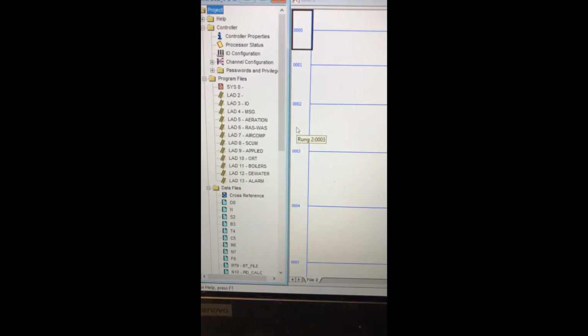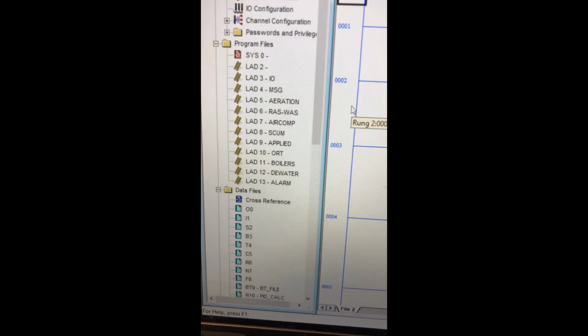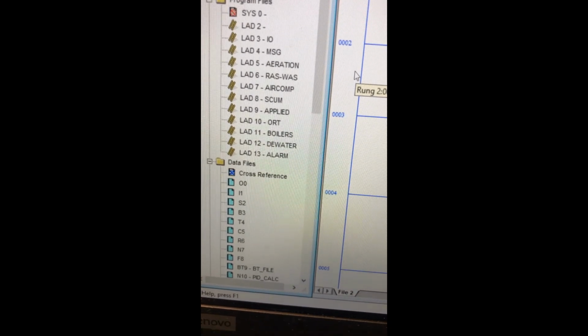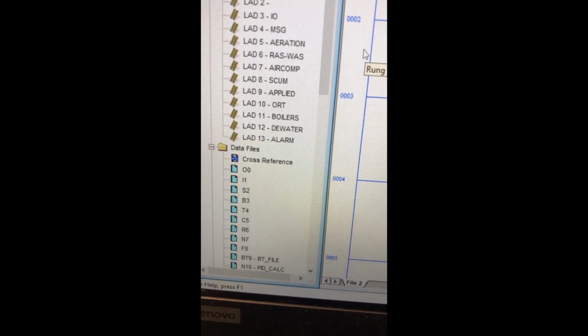So this is where I do all the PLC programming. This is what the software looks like for Allen-Bradley. And this particular program here is for PLC-B. That was the larger one that we looked at earlier in the tour, at the very beginning, back where the blowers were, and the blower starters and the power distribution. And you can see there's quite a few processes in this PLC. We're controlling aeration, the RAS-WAS, the air compressor system, the scum pump, the applied pumps, the odor reduction towers, the boilers, the centrifuges, dewatering, and of course we have some logic that we have to perform for the alarm system here.